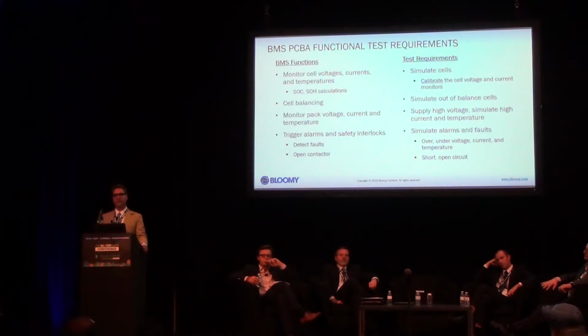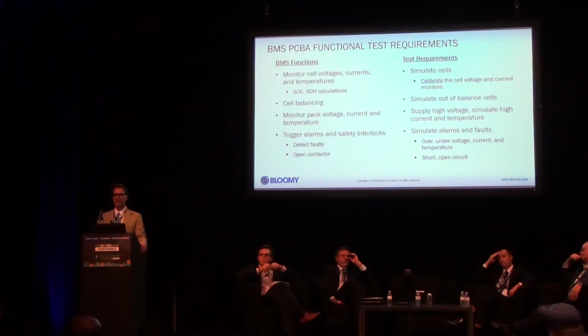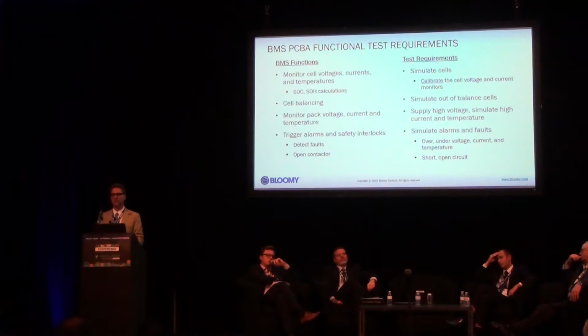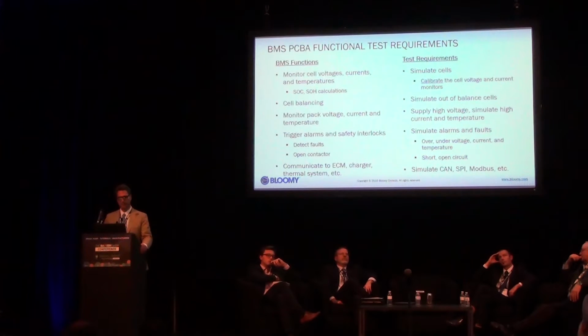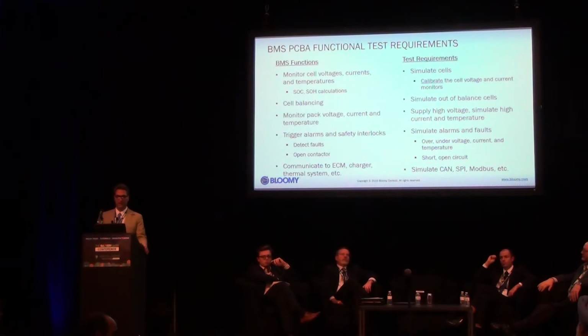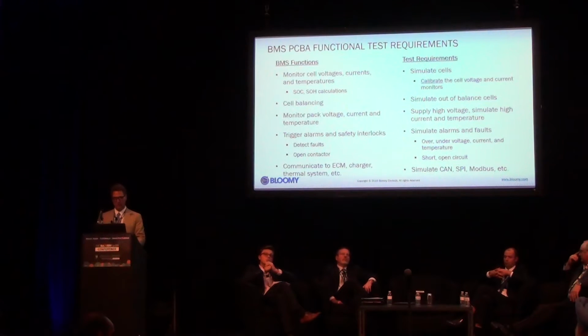And so the functional tester should simulate those alarms and faults by simulating over and under voltages, over and under current, and over and under temperature on each and every individual cell. Simulate opens and shorts on each cell, and verify that all of these alarms and safety interlocks are triggered on the BMS. And then finally, the BMS must communicate digitally to the ECM, charger, thermal system, other ECUs, etc. And so the test system needs to simulate or provide CAN communications or SPI or LIN or Modbus or whatever is necessary in order to test that functionality.